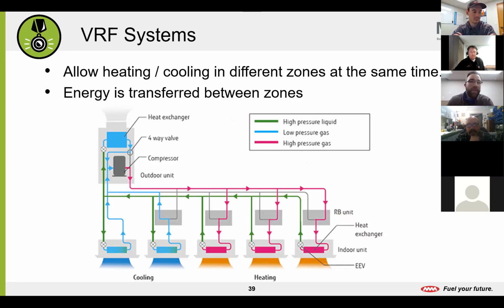So main points of a VRF system or variable refrigerant flow system. I know Daikin likes to call them VRVs, which is variable refrigerant volume. The reason why we have them is it gives us true zone control, right? We can have multiple zones. If you look at the picture here, we have 5 indoor units. 1, 2, 3, 4, 5.